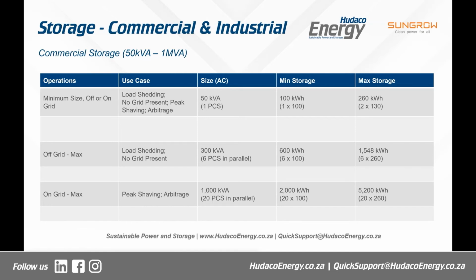This is important. In off-grid mode, we have a maximum of 6 units which we can put in parallel, 6 PCSs in parallel, which means we can create a grid of up to 300 kVA, with battery storage between 600 kilowatt hours and 1.5 megawatt hours. And operating in on-grid mode, however, we can actually go up to 20 PCSs. In other words, we could have a 1 MVA system providing between 2 and 5 hours of storage, so between 2,000 and 5,200 kilowatt hours there.